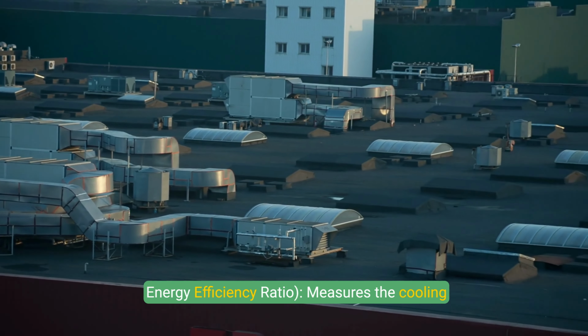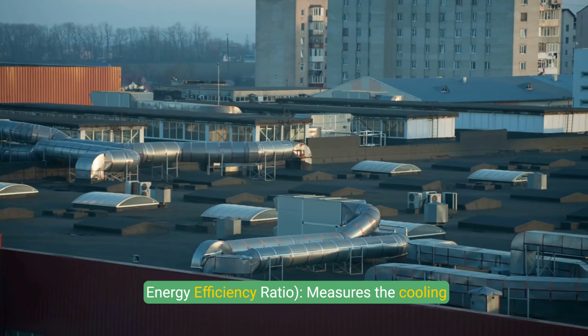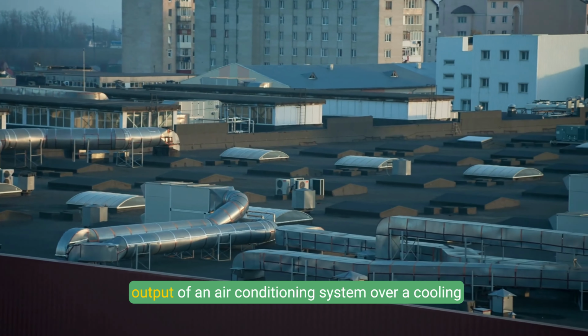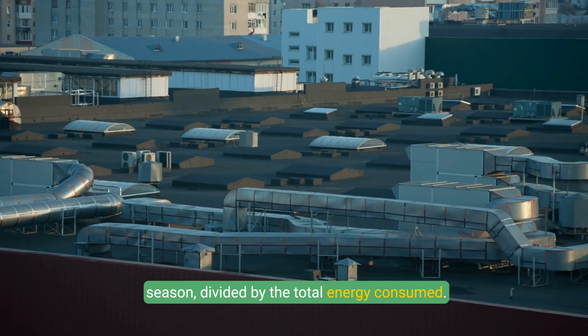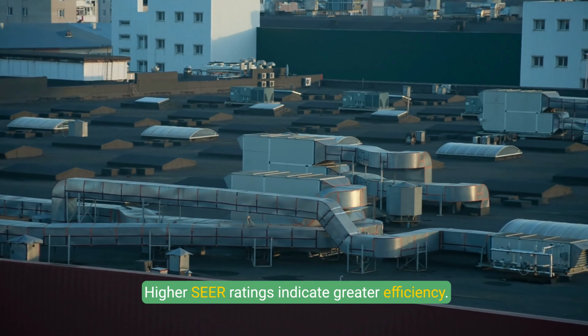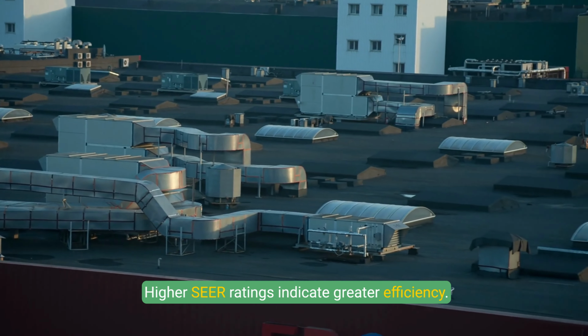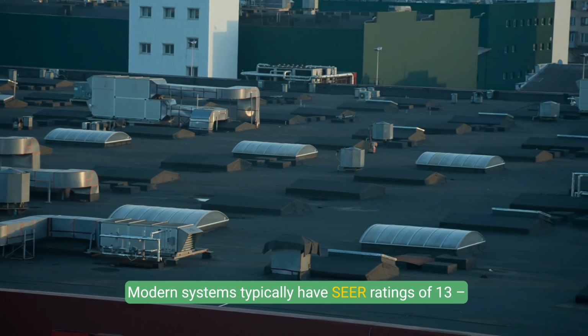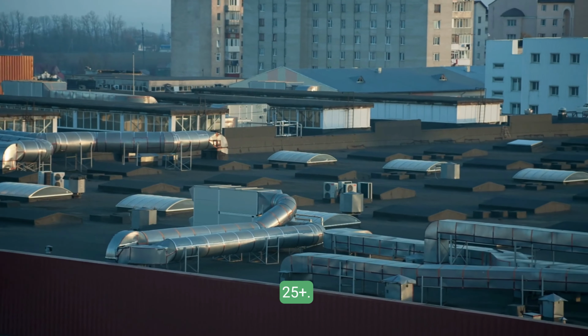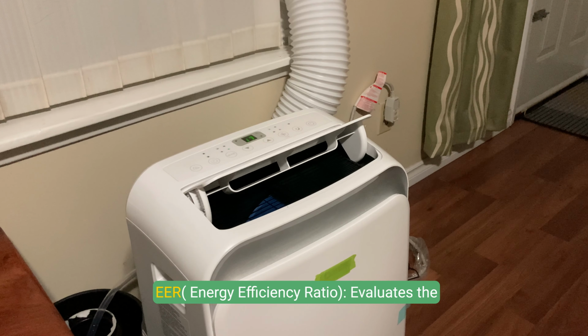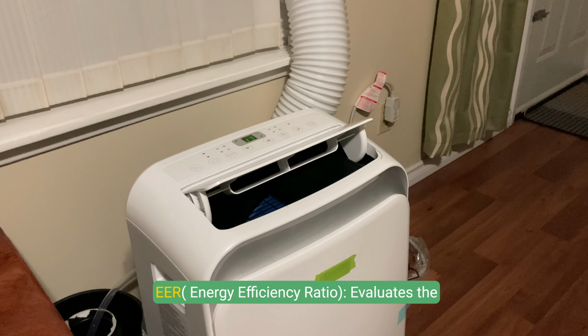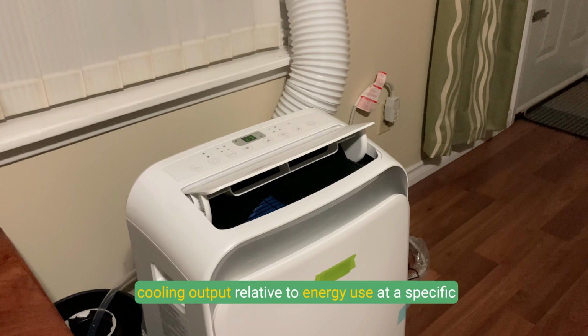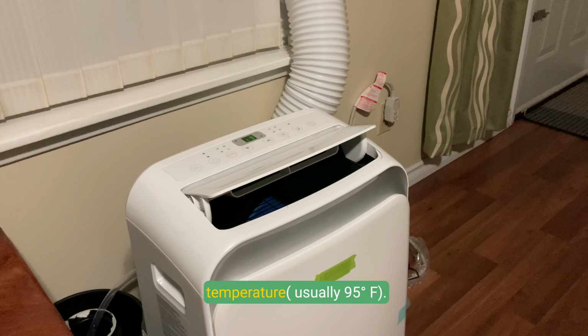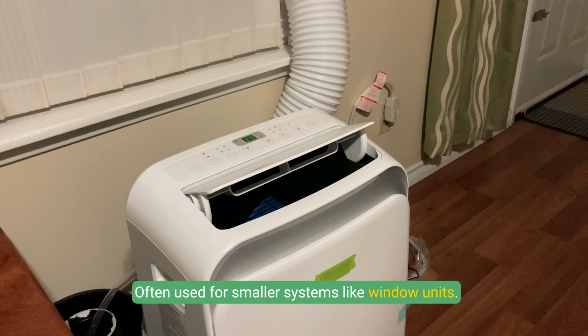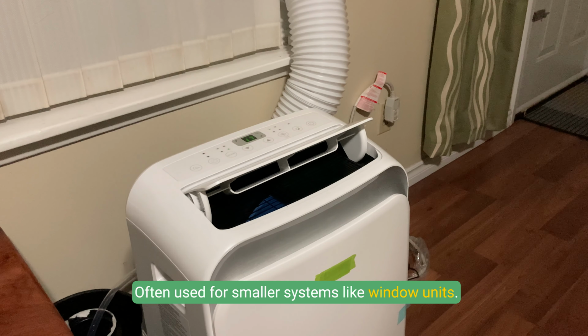SEER, Seasonal Energy Efficiency Ratio, measures the cooling output of an air conditioning system over a cooling season, divided by the total energy consumed. Higher SEER ratings indicate greater efficiency. Modern systems typically have SEER ratings of 13 to 25 plus. EER, Energy Efficiency Ratio, evaluates the cooling output relative to energy use at a specific temperature, usually 95 degrees Fahrenheit, often used for smaller systems like window units.